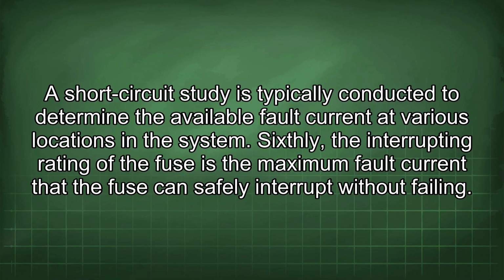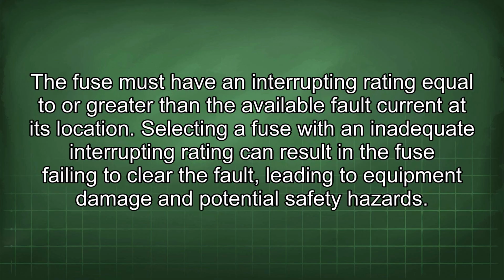Sixthly, the interrupting rating of the fuse is the maximum fault current that the fuse can safely interrupt without failing. The fuse must have an interrupting rating equal to or greater than the available fault current at its location. Selecting a fuse with an inadequate interrupting rating can result in a fuse failing to clear the fault, leading to equipment damage and potential safety hazards.